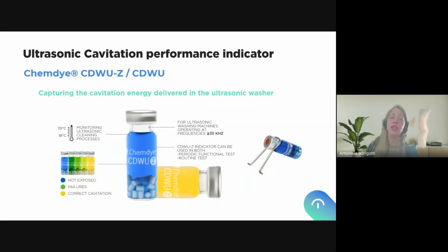And this is the reason why we have this ultrasonic cavitation performance indicator. This indicator, ChemDye CDWU-Z or CDWU, are indicators. Both of them are very similar. There's a very little difference. What you see in the screen is the version Z. This one is a glass ampoule with the blue reactive solution with ceramic cylinders immersed in it. Initial color is blue. The yellow you see also is the final color, but the initial color is blue. The CDWU is exactly the same, but instead of having ceramic cylinders inside, it has glass beads or pearls. It's just a material and format difference due to patent reasons, which no longer exist. So both of them are completely the same and can be perfectly used everywhere.